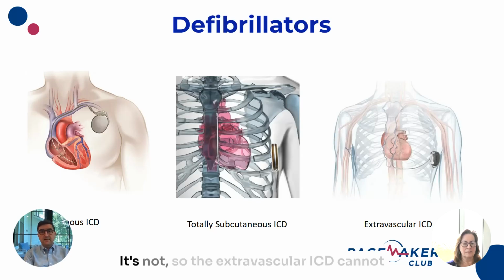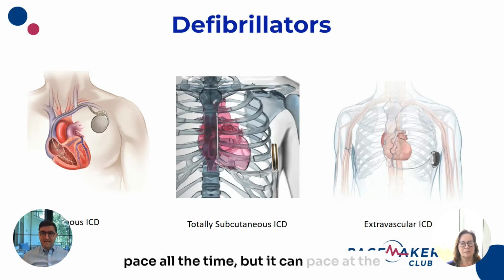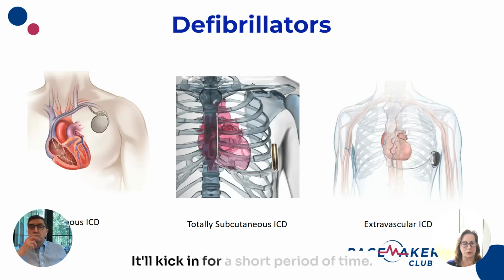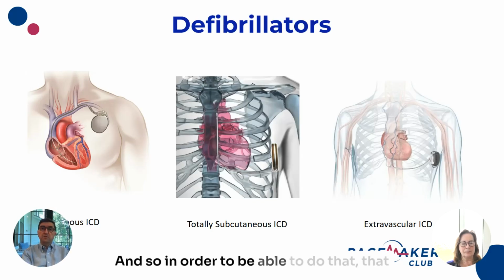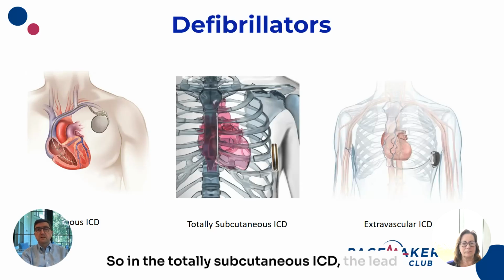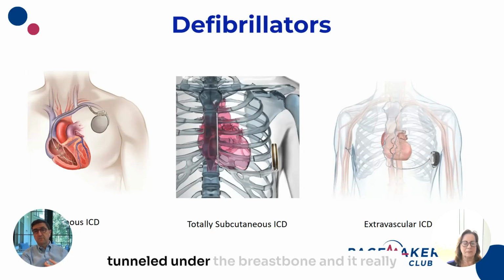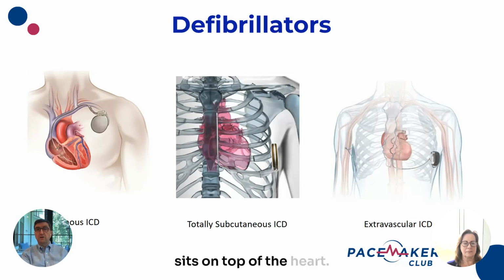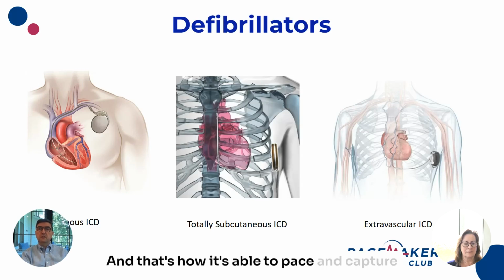So the extravascular ICD cannot pace all the time, but it can pace at the time of its detection of ventricular tachycardia. Yeah, so it senses that rhythm, it'll kick in for a short period of time. Correct. And in order to do that, the lead has to be put under the breastbone. In a totally subcutaneous ICD, the lead is tunneled under the skin outside of the breastbone, whereas with the extravascular ICD, the lead is tunneled under the breastbone, and it really sits on top of the heart, and that's how it's able to pace and capture and generate an evoked potential in the muscle.